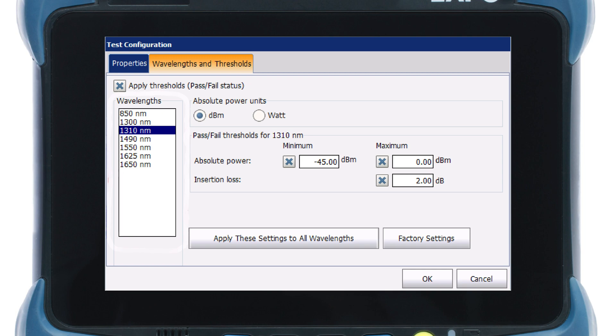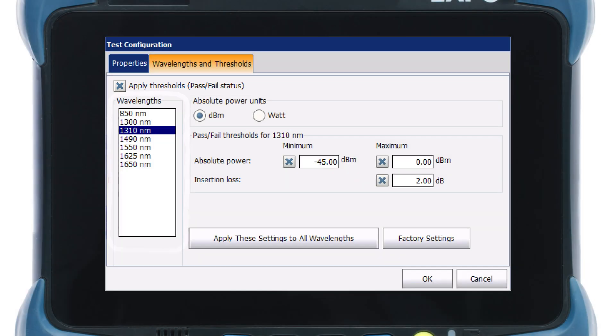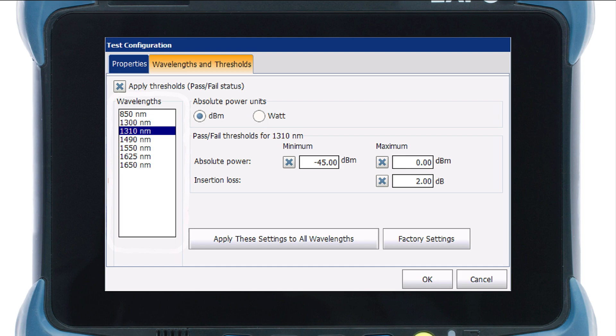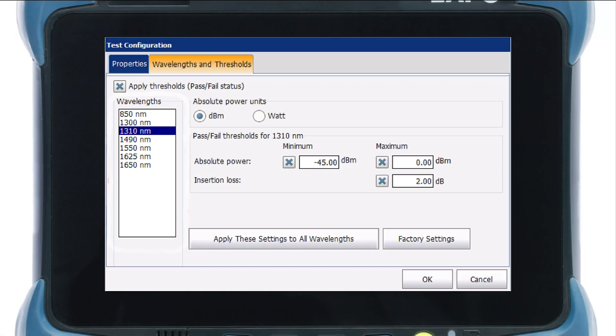Select Apply Thresholds, Pass and Fail status to apply the thresholds and display the relevant information in the Instrument View tab of the main window. From the Wavelengths list, select the Wavelength for which you want to set a Threshold. And then, modify the values as needed.